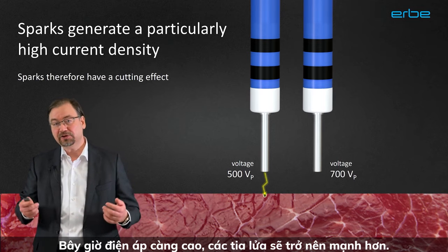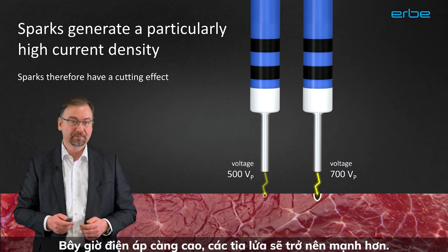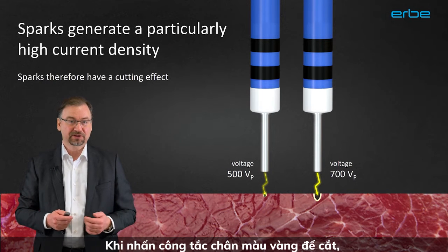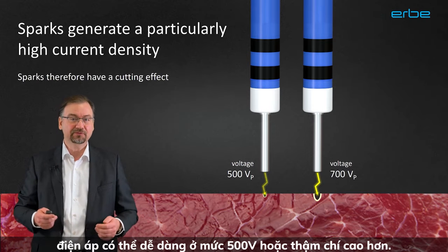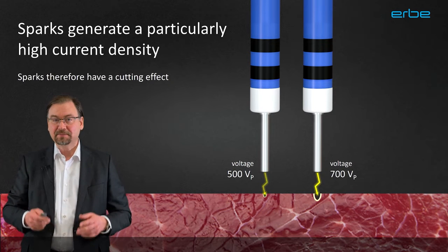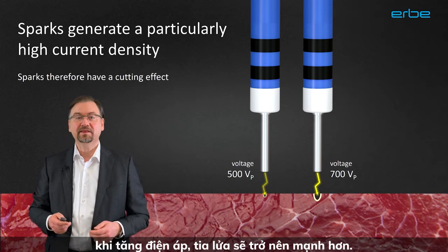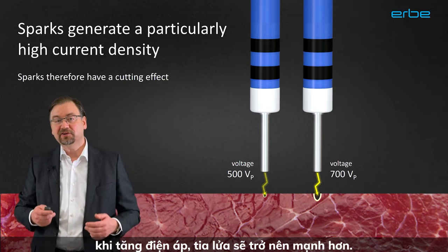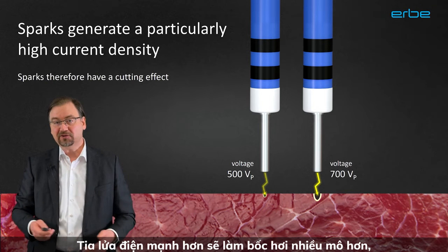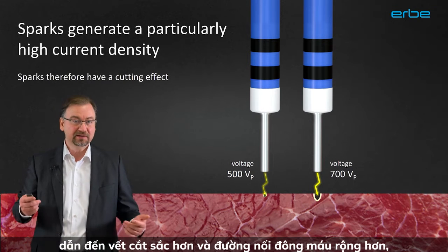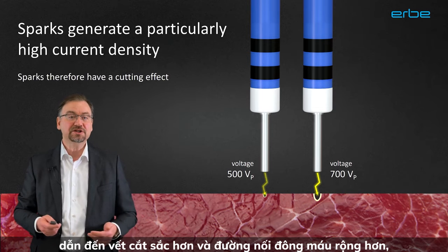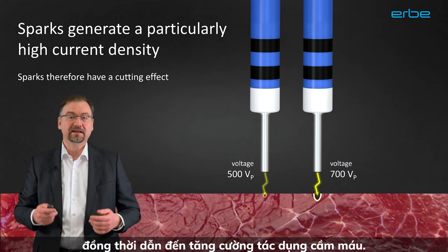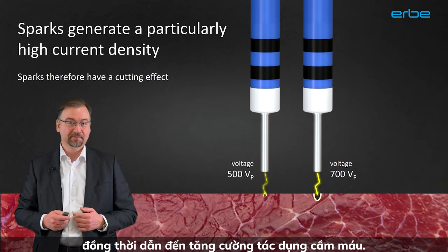Now, the higher the voltage, the stronger the sparks will become. When you press the yellow foot switch for cutting, this can easily be some 500 volts or even higher. Depending on the selected mode, usually when the voltage is increased, the sparks become stronger. The stronger sparks will vaporize more tissue, resulting in a sharper cut and a wider coagulation seam, and also resulting in an intensified hemostatic effect.